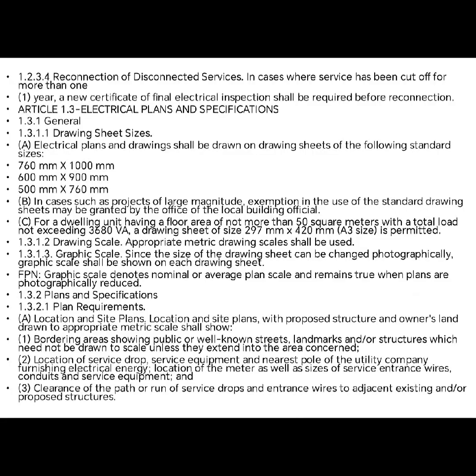1.3.1.2 Drawing scales. Appropriate metric drawing scales shall be used. 1.3.1.3 Graphic scale. Since the size of the drawing sheets can be changed photographically, graphic scale shall be shown on each drawing sheet. FPN. Graphic scales denote nominal or average plan scales and remain true when plans are photographically reduced. 1.3.2 Plans and specifications.